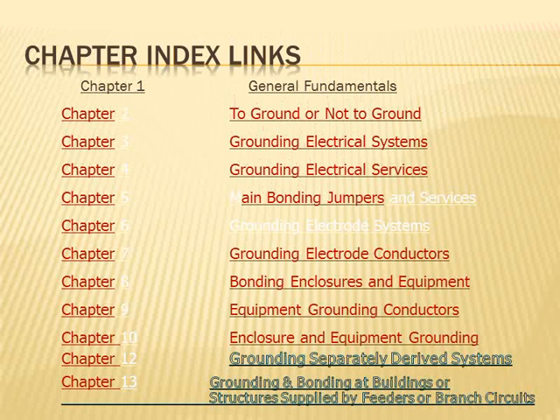to the ground. So that's what we mean when we talk about bonding enclosures and equipment. And to ground the equipment, we have the equipment grounding conductor that does this job for us, an enclosure and equipment grounding. So these are a couple of things about most of these chapters: grounding the system versus grounding the equipment and tying the two together. Separately derived system, I'm going to go over these one by one, guys, with the pictures that I have.